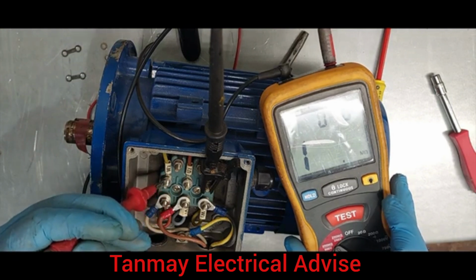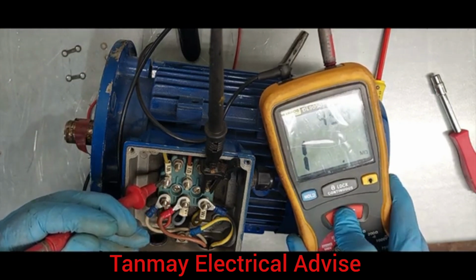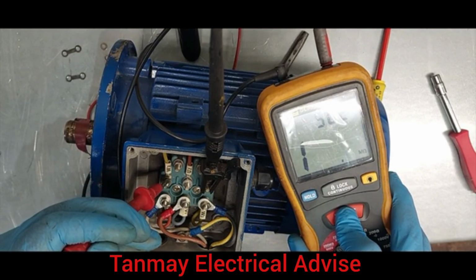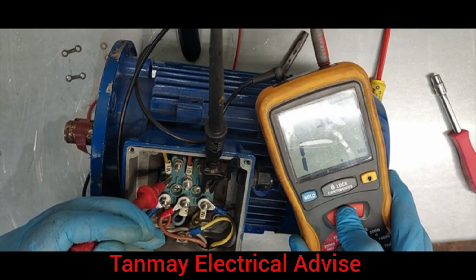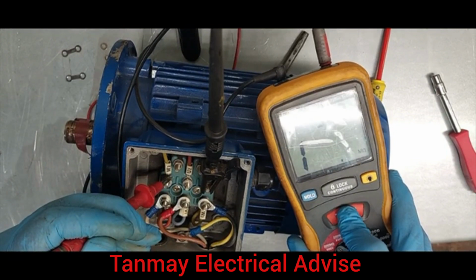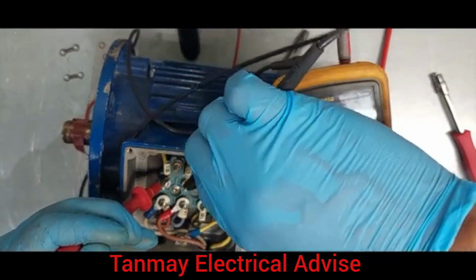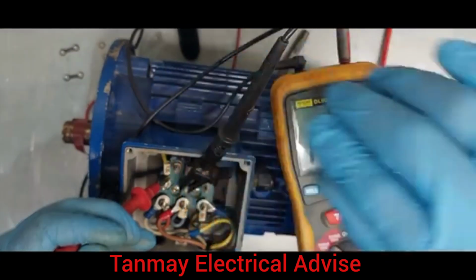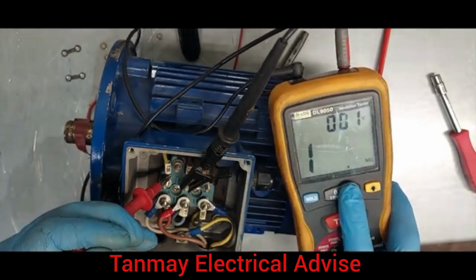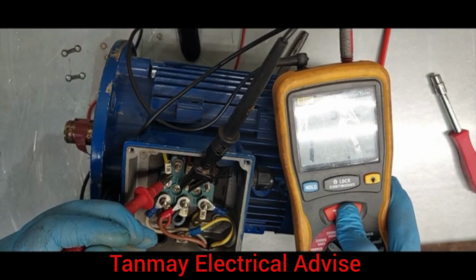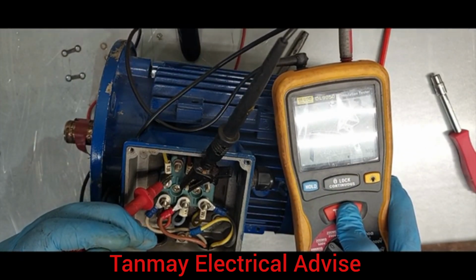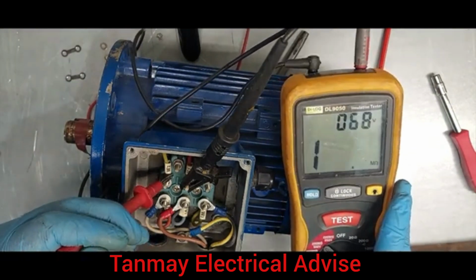We do the same between V2 and W2. We see that the insulation is good, 1 mega ohm. It's high enough. Then the final test, we have to do U2 and W2. We inject 500 volts, and we have 1 mega ohm, which is good.